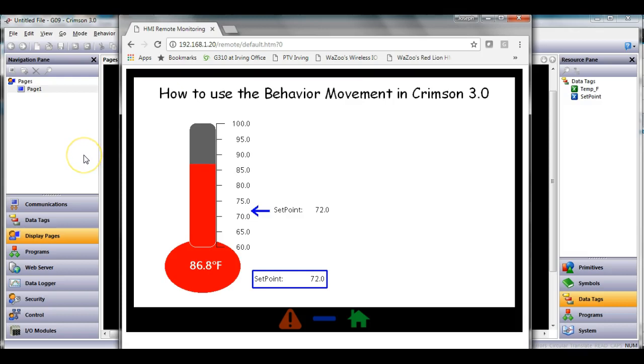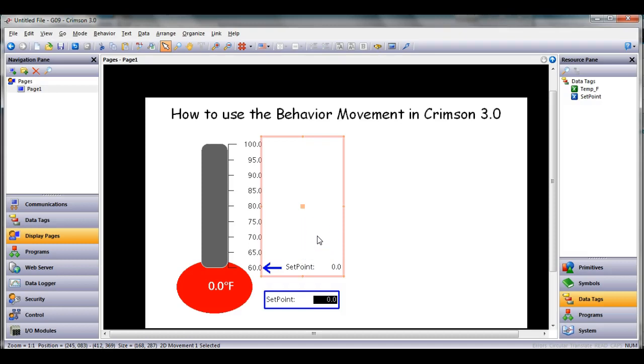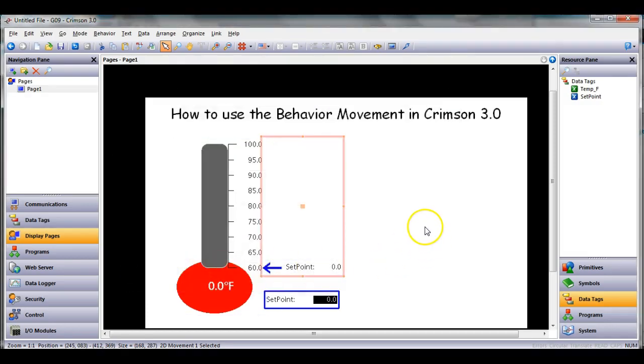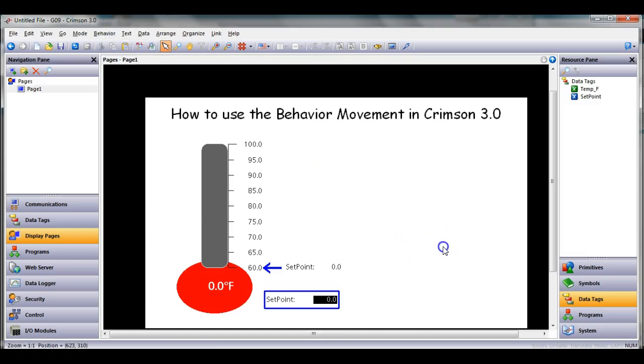That's just a quick easy way to use the behavior movement in Crimson 3. The one important part of this is on your graphic, the part that everybody forgets, is when you right click on the properties of your 2D movement, which you would have gotten by the behavior pulldown, you've got to link it to the tag. The vertical will go up and down, the horizontal will go left and right. They also have another movement function called 2D polar movement which you can really move things all around.